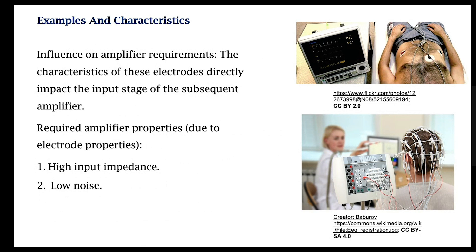We are interested in having high input impedance and low noise — but why high input impedance? Because otherwise there will be loading of the signal. If you know basic electrical engineering and Kirchhoff's laws, you know that current flows through resistances that are lower in value. So if the amplifier has high input impedance, the amplifier itself will not act as a load to the electrode — this is absolutely critical.